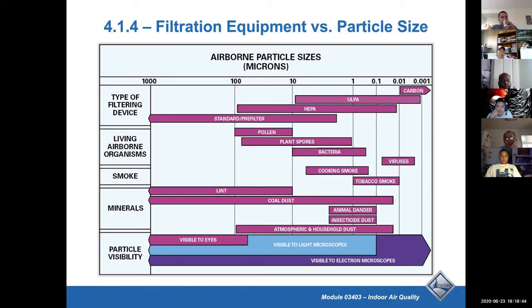This one thing we talked about, filter equipment. For COVID-19, did they tell you guys anything about filtration for your buildings? Anybody? No? Our corporate company is in California, and they're asking us to put in a higher MERV filter because we're using MERV 8 filters on our air conditioning equipment. They want us to go up to MERV 13 or 14. The only problem is that it really increases the cost of your filters.